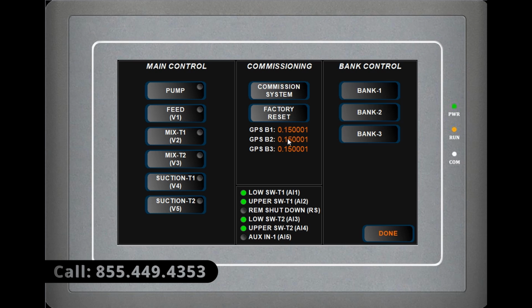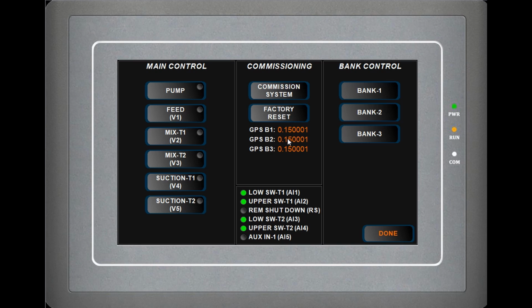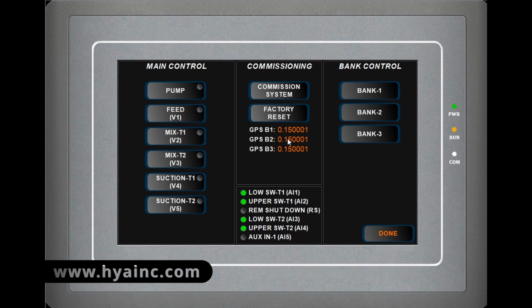So you really do want to do the auto commissioning process - that will be covered in another tutorial. But prior to commissioning the system, you want to make sure the valves are opening and closing like you'd expect, and that the volume feedback is coming in as expected.